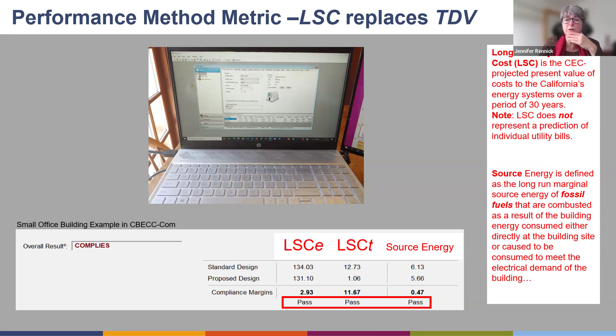That energy system is going to be looked at over a period of 30 years. And then we're going to have source energy, which is the long-run marginal source energy of fossil fuels burnt or combusted, either because the building uses the fossil fuel directly, like a gas furnace, or because it's burnt to create the electricity the building uses, as in those peaker plants we use to generate electricity. If all three of those components pass, then your building will comply and pass.